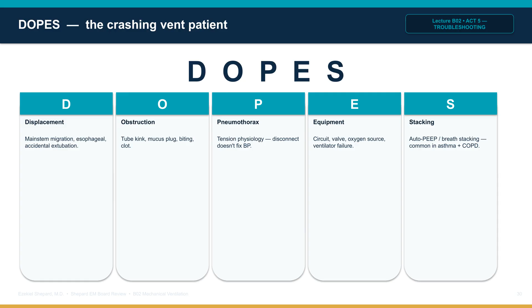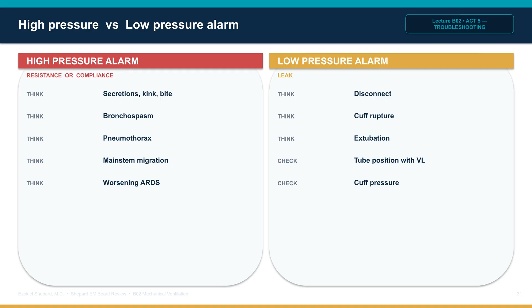Differential: secretions, mucus plug, kinked tube, biting on the tube, bronchospasm, tension pneumothorax, mainstem migration, worsening ARDS. Low pressure alarm, the less common. The ventilator is meeting less resistance than expected, usually because air is escaping. Differential: circuit disconnection, cuff rupture, accidental extubation. The alarm is your friend, it is information. Silence it only after you have figured out the cause.